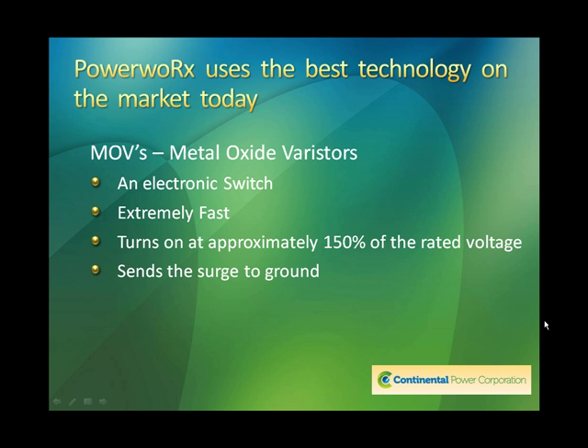Metal oxide varistors, think of it this way. It's like an electronic switch. It's extremely fast. I use the analogy of a sentry, a guard, who is standing by the panel, literally with his hand on the panel monitoring the voltage. And when the voltage goes above the level that is set for the MOV, that sentry flips a switch, and that switch will connect that power line to the ground line. And so all the energy that is above that preset level ends up getting diverted off to ground.